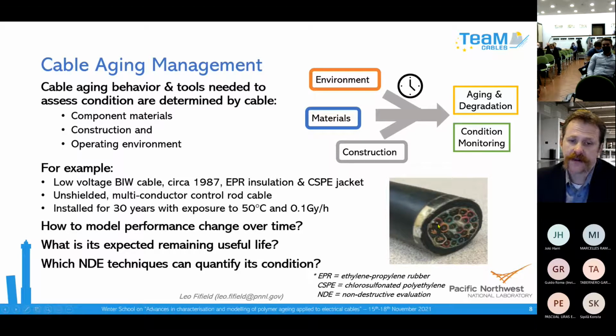In the last practical, there were questions about the bonding of insulation, the connection, and the orientation of insulated conductors next to each other. Those things affect some of the tools that can be used to assess the condition of the cable. All these factors, along with how long they've been in service under those conditions, affect the aging degradation and how we can quantify and monitor the condition.